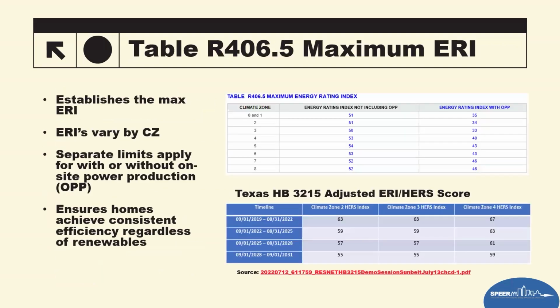And then the ERI, we talked about that a second ago. The table you see on the right-hand side top is what's out of the book. What we see on the lower right is what Texas adjusted by House Bill 3215. So as I'm saying this and going through it, the top table is what's in the code book. Right now, Texas has the House Bill 3215, which adjusted it until September 1 of 2031. Right now, we're currently in the third adjustment for the timeline, which puts climate zones 2 and 3 at 57 and climate zone 4 at 61.